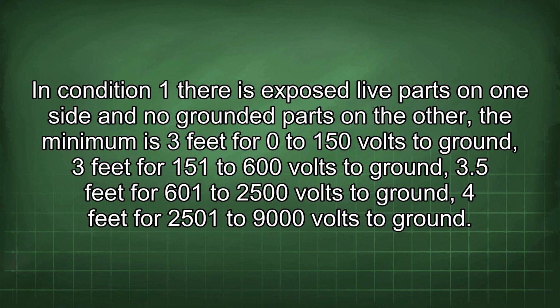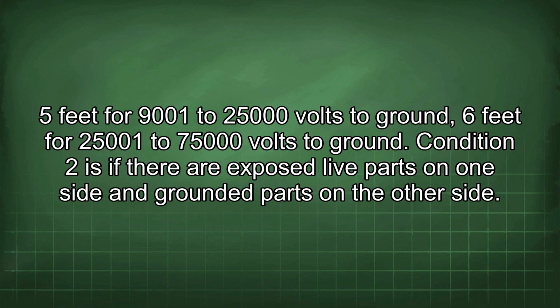The minimum is 3 feet for 0 to 150 volts to ground, 3 feet for 151 to 600 volts to ground, 3.5 feet for 601 to 2500 volts to ground, 4 feet for 2501 to 9000 volts to ground, 5 feet for 9001 to 25,000 volts to ground, 6 feet for 25,001 to 75,000 volts to ground.